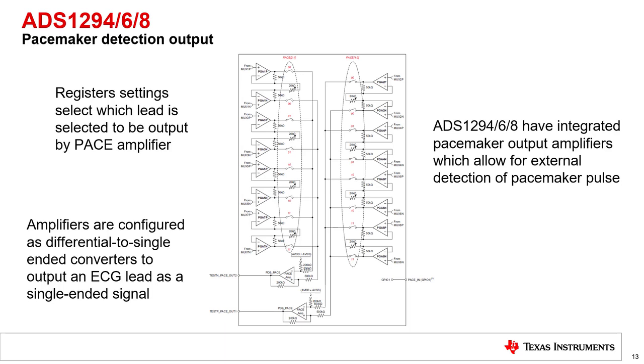The ADS1294, 6, and 8 include a circuit to facilitate pace detection. The device allows the user to choose which ECG channel is selected for pace detection, as you can see from the circled part of the diagram. That channel input is sent to the pace amps, which are differential to single-ended converters. The output is connected to pins on the device. This allows the users to create their own pace detection circuit outside of the ADS129X.